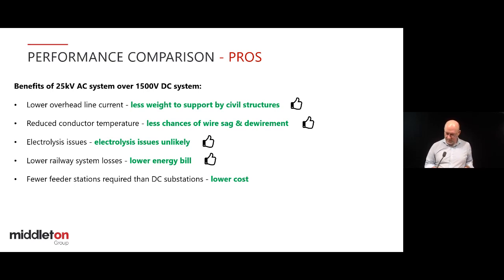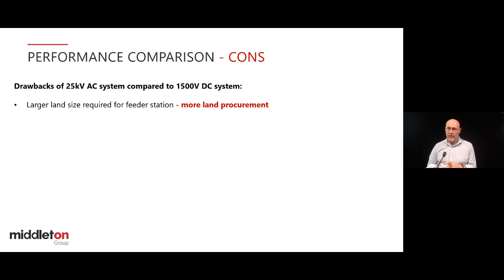But this will be shown in the next slide to be also slightly negative. So there are fewer substations, but each of those substations, here's some cons, is slightly bigger. So instead of having a 10 by 20 metre substation, but lots of them, you'll have a few, say 50 by 50 metre substations. They can be made fairly compact. SFCs make them more compact, but you have a lot fewer substations, 2 or 3 on a 25 kV system versus 30 or more on a DC system. So the difference is a few big ones versus trackside smaller ones, but generally the pros outweigh the cons overall in land use.